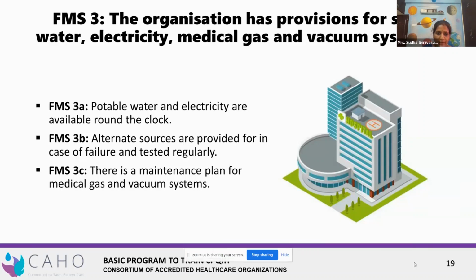FMS 3B says alternate sources are provided in case of failure and tested regularly. In case the main sources for electricity or potable water fail, do you have alternate sources so that patient care is not interrupted? And for those alternate sources, do you test regularly, in case those also fail? So there are multiple checks and controls expected as per the standards in terms of electricity, water, and medical gas supply.